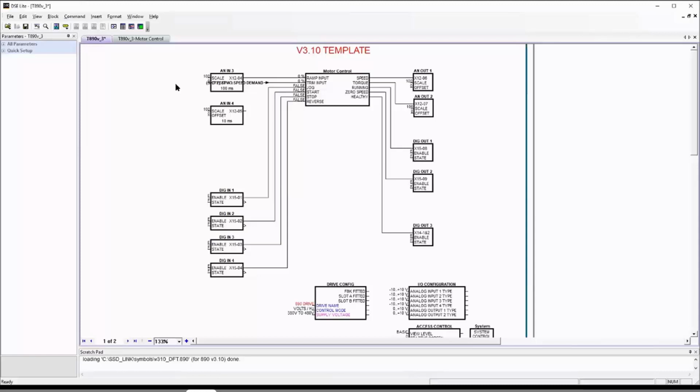You can put them on a monitor list in text, and you can add as many parameters as you want in that list. You can put that parameter and view it as a chart to see a trend. And in the 890 and AC30 P and D versions, you can actually view it in an oscilloscope in real time.